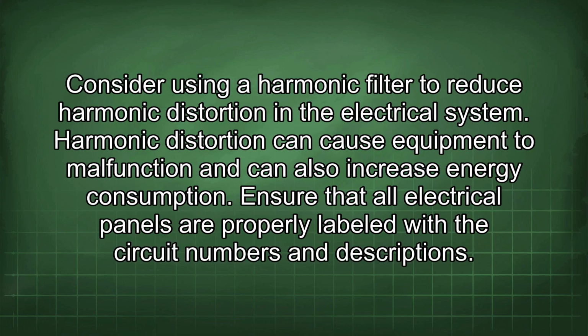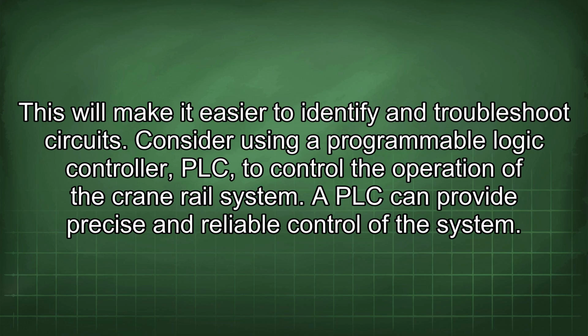Consider using a harmonic filter to reduce harmonic distortion in the electrical system. Harmonic distortion can cause equipment to malfunction and can also increase energy consumption. Ensure that all electrical panels are properly labeled with the circuit numbers and descriptions. This will make it easier to identify and troubleshoot circuits.